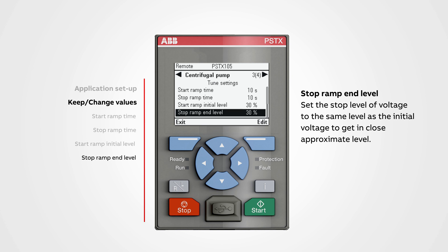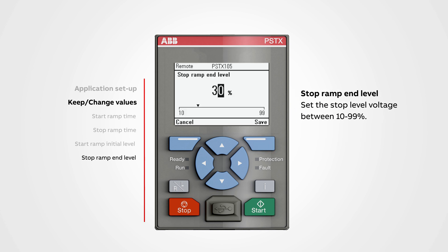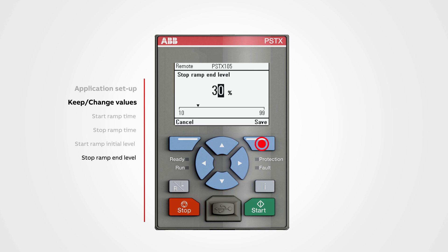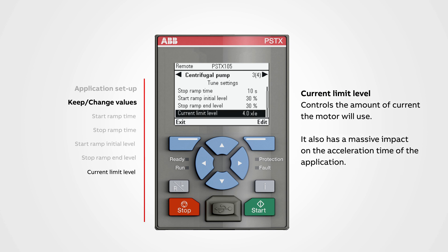Stop ramp end level sets the stop level of voltage to the same level as the initial voltage to get a close approximate level. The stop level voltage can vary from application to application, but it is a good rule of thumb to match it. To change a value, push edit. We can set the stop level voltage between 10 to 99 percent. Use the navigation buttons to change the value, then push save.